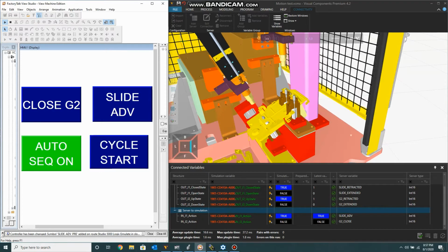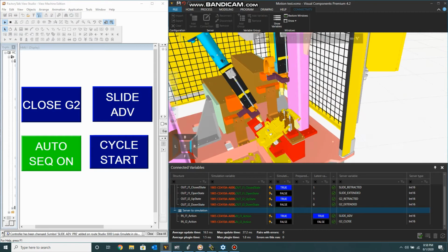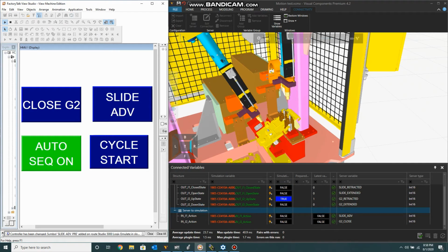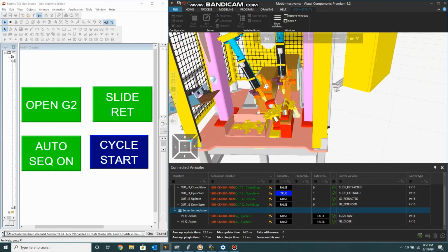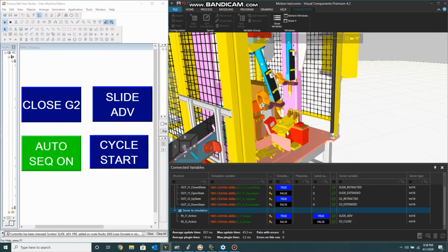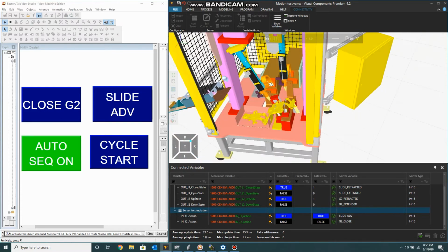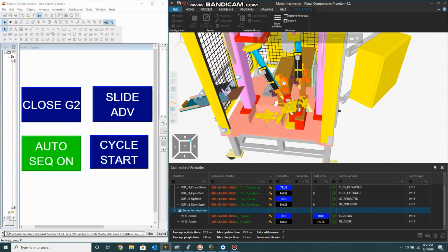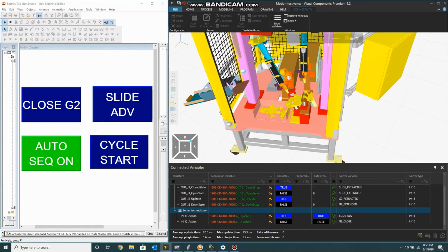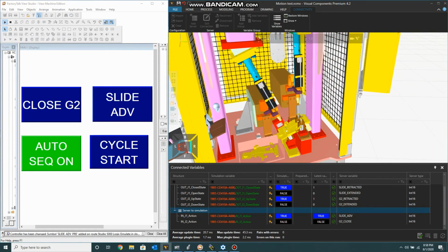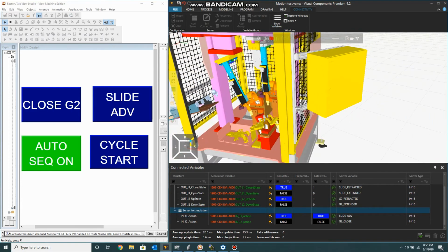The cool thing is that the only tags that we have to connect between the emulator and the simulation are just the output tags, like on an actuator on the fifth rung, or after the preconditions and the safety and all that, after the command rung. When we actually send the output, we just need to map that to the signal in the simulation that will move the virtual components, just as if we were mapping it to a valve bank, and it'll work just fine.